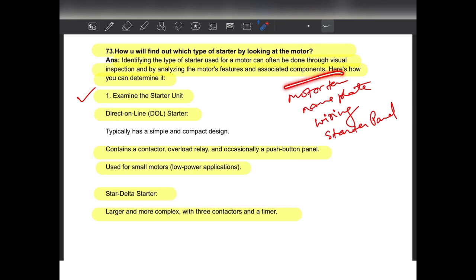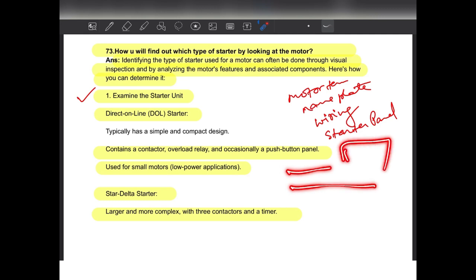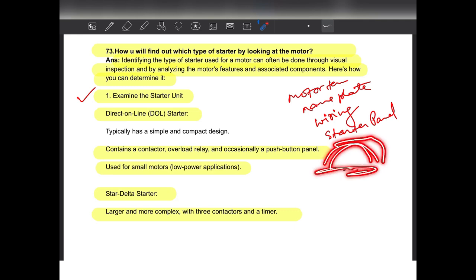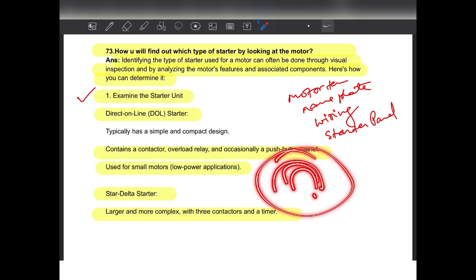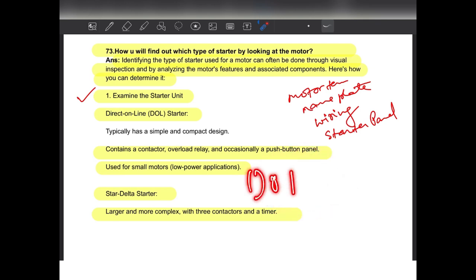First of all, you look at the motor; sometimes the nameplate also shows which type of winding is needed for the motor, star or delta or some other type of wiring. Then you look at the starter unit. A direct online starter has a very simple circuit. A star delta starter has timers and relays, a star contactor, and a main contactor. We short the three wires at the star contactor. So you look at the starter and you can tell whether it is a direct online or star delta.